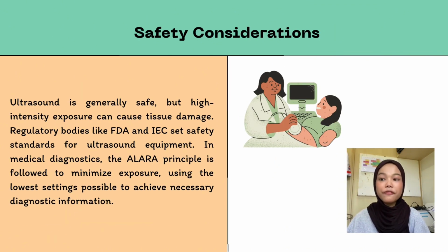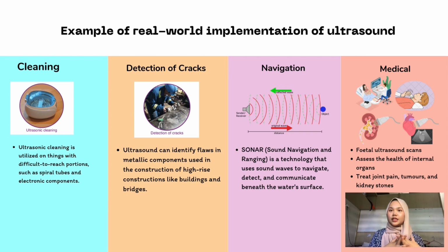Lastly, for safety considerations, ultrasound is generally safe, but high-intensity exposure can cause tissue damage. Regulatory bodies like FDA and IEC set safety standards for ultrasound equipment. In medical diagnostics, the ALARA principle is followed to minimize exposure, using the lowest settings possible to achieve necessary diagnostic information. Next, we move to an example of real-world implementation of ultrasound.